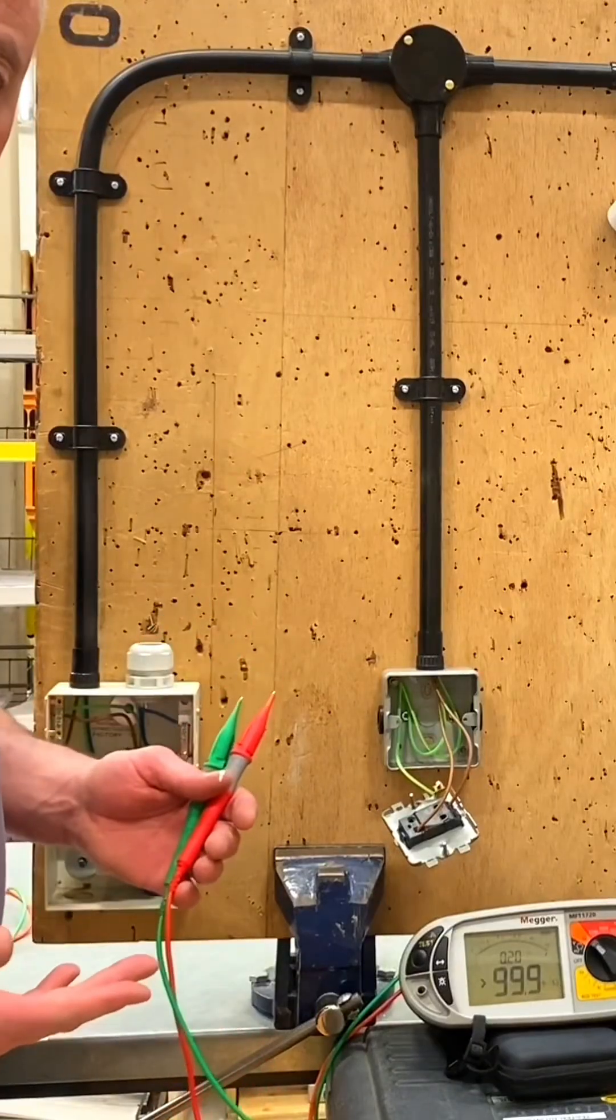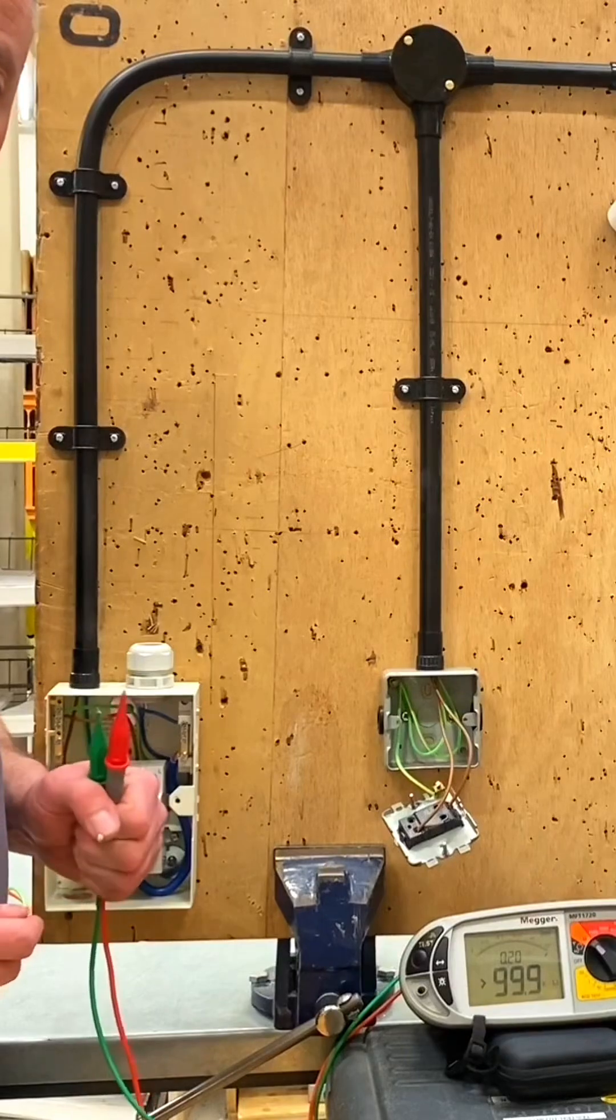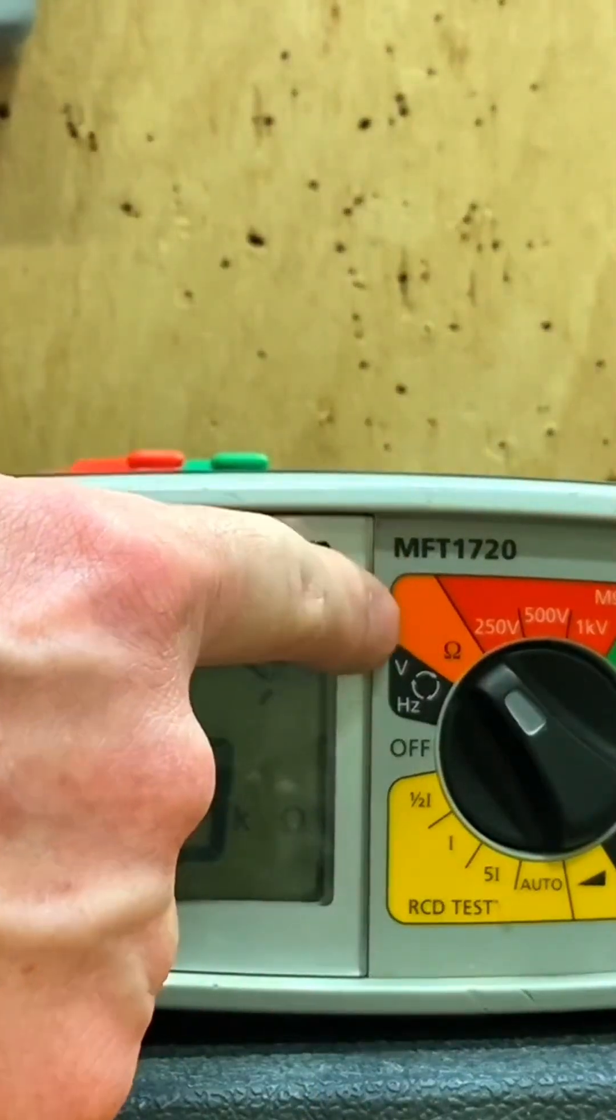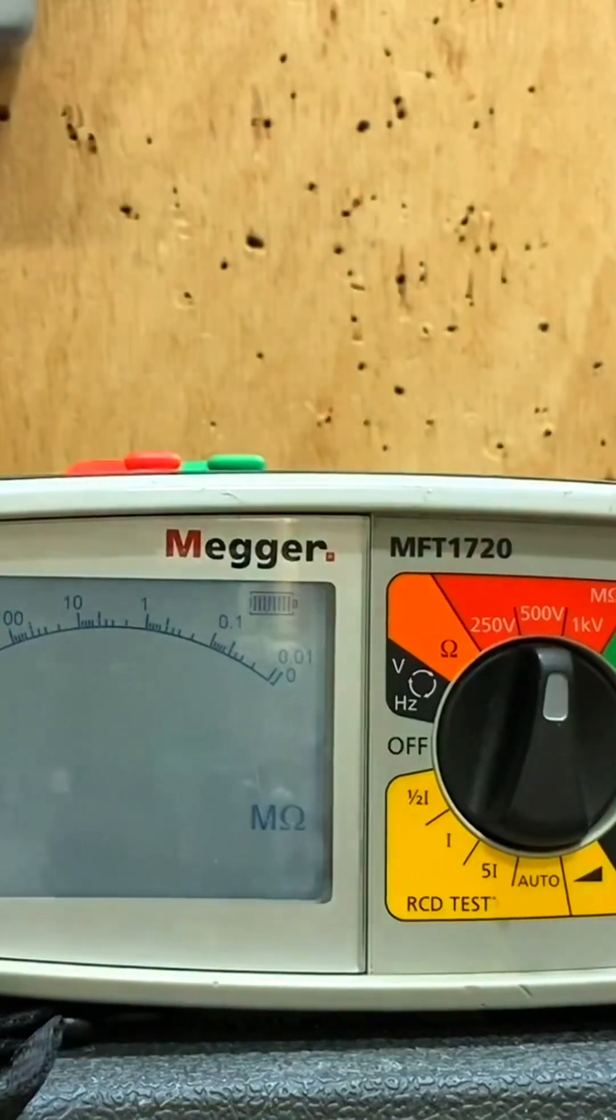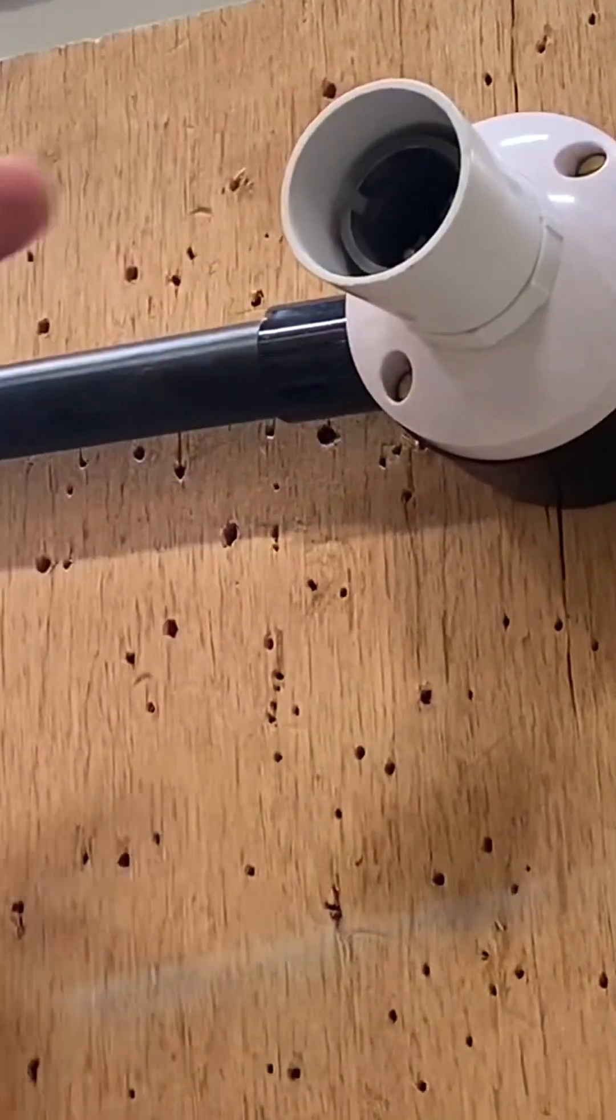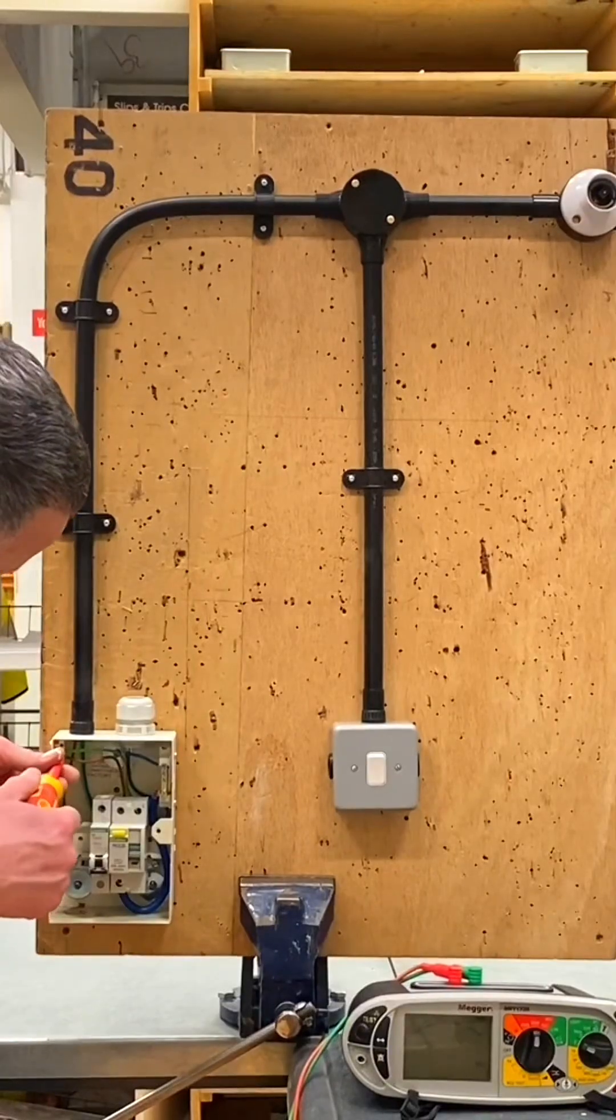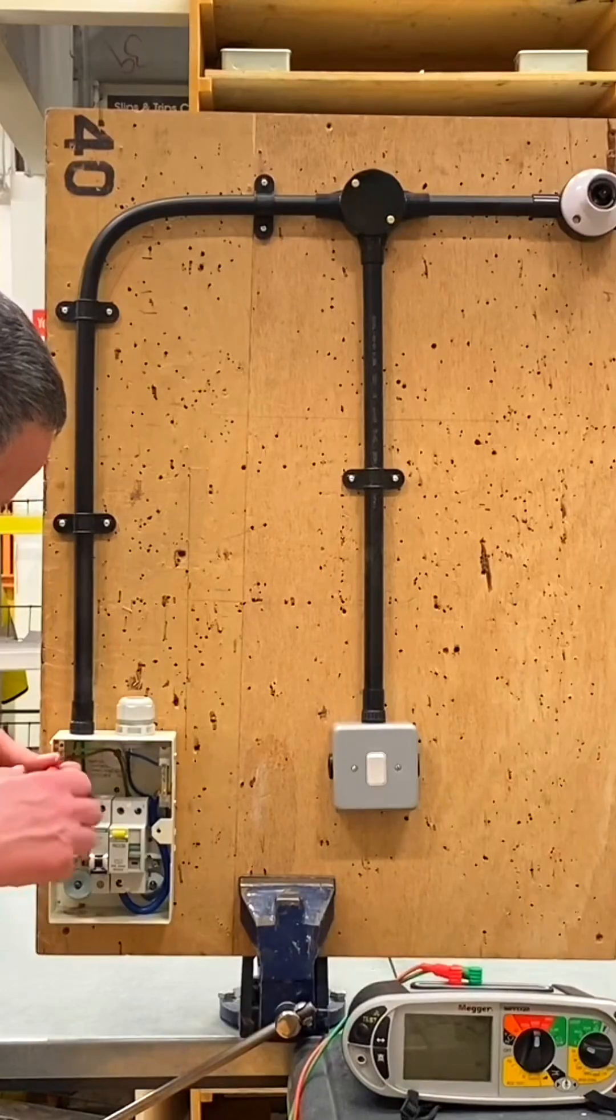Now we need to put all the covers back on, leave the switch in the on position so we can carry out our insulation resistance test next. Let's change our instrument from ohms - we're measuring the resistance of the conductors for continuity - to the mega ohm scale. We're going to be testing at 500 volts DC to perform our insulation resistance test on our 230 volt lighting circuit. We've put the covers back on, our load's been removed so we've got no lamps in circuit, our switch has been left in the on position.